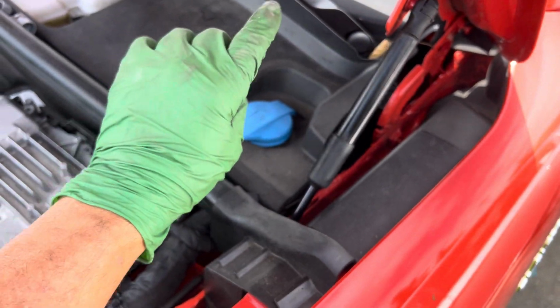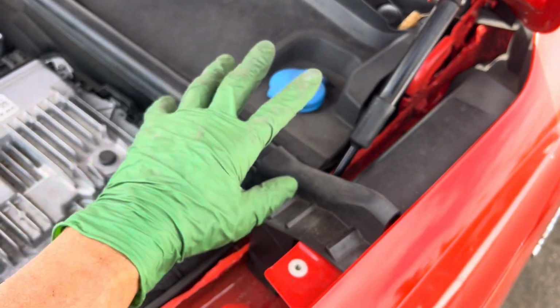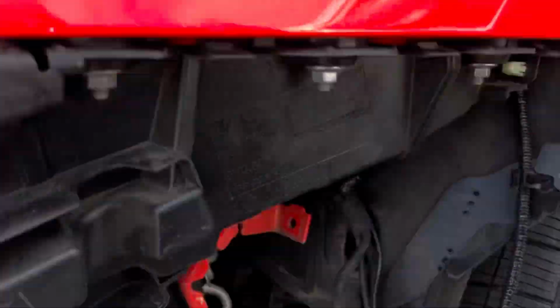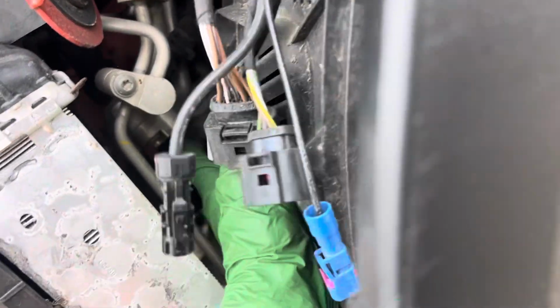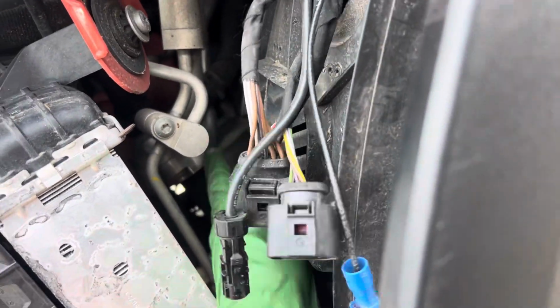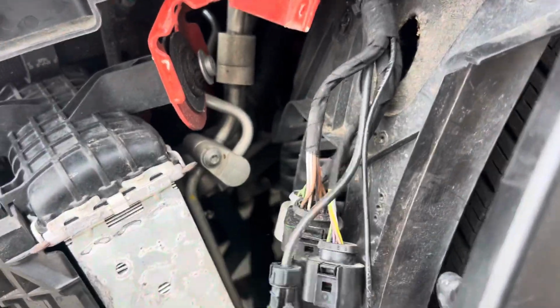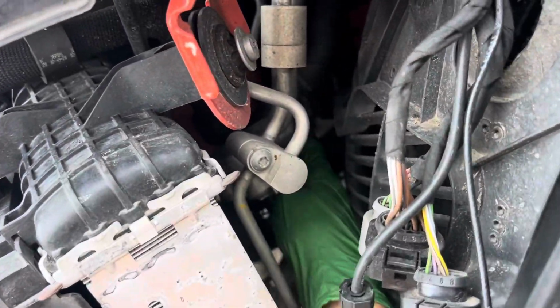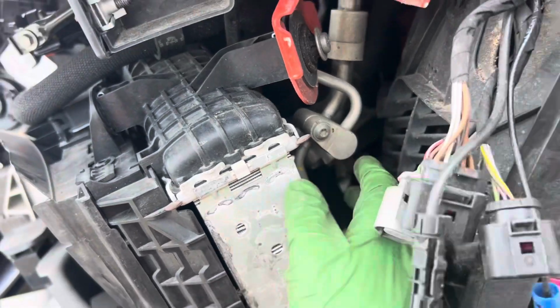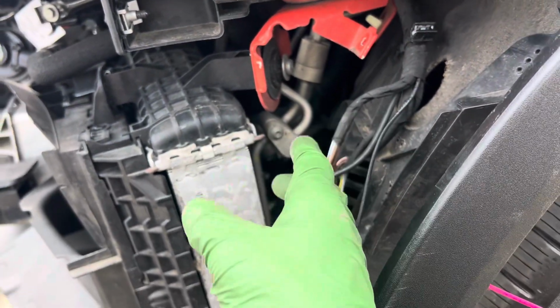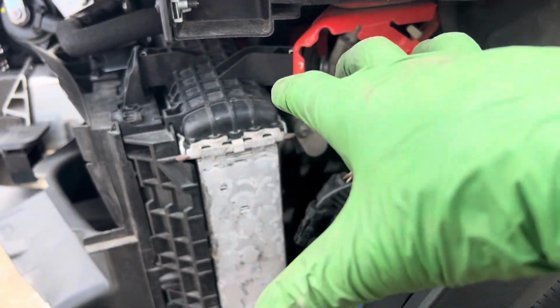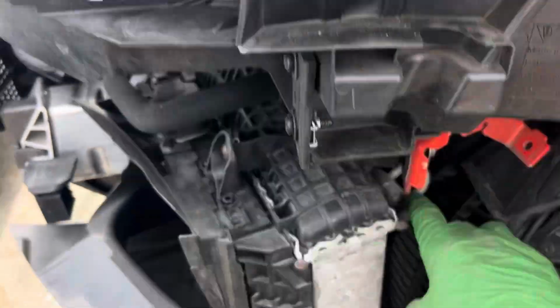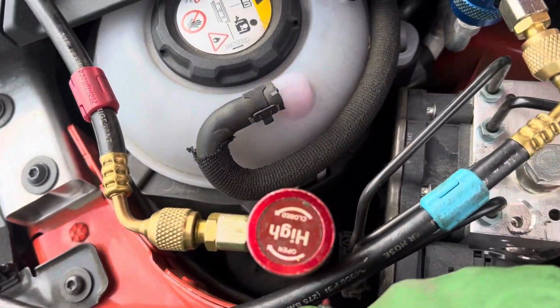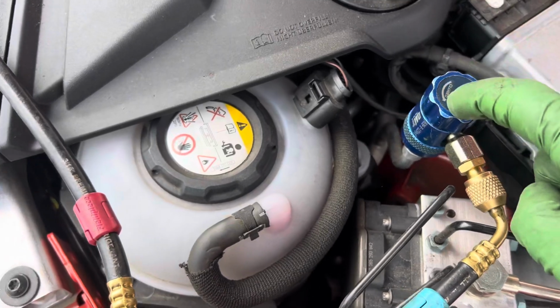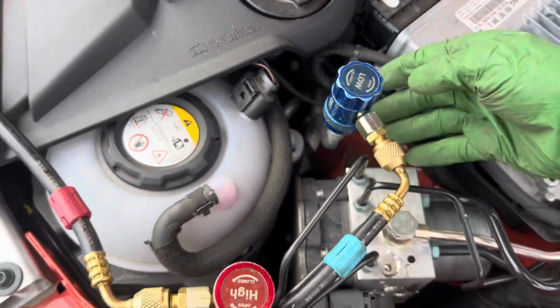It condenses, goes to saturation, the oil and refrigerant come back down here, dump right here at this little J, and it acts as an oil trap and refrigerant trap. So this whole section of line right here fills up with oil and refrigerant once it turns back into liquid from a vapor, and it dumps right there. Well, that other line, it comes right up to the suction right here.